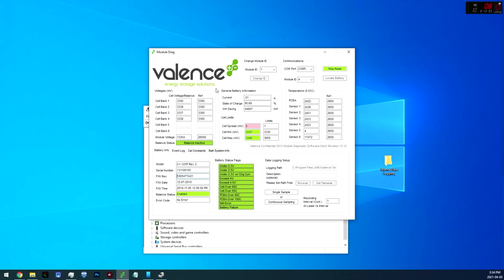Okay, so a couple more values that it has is it gives you the voltage of each cell bank. So there's 12-volt battery, so there's 4 cell banks. So this is the voltage, so it would be 3.3 volts. And over here you can change your reference voltage, whatever you want to set your reference to, you can. And over here you have your cell spreads. So you can set your limit in that config file that I showed you earlier. So you would set your cell spread limit in the config file before you open the software. So just for testing, I just set it to 1. So if it goes any higher than 1, the box will turn red to kind of give you a visual alert that the cell spread is too high.